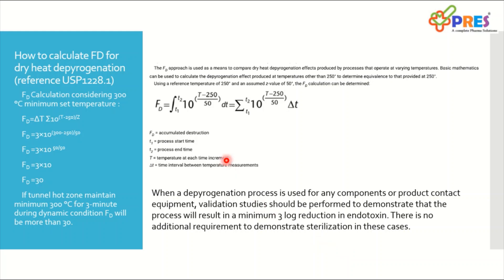Here is the formula for calculating the FD value: from time T1 (starting process time) to T2 (end process time), the integral of 10 to the power of (T minus 250) divided by 50, multiplied by delta-T (the time interval between temperature measurements). For example, if the set temperature is 300°C and exposure time is 3 minutes, the FD will be 30. This FD will vary based on changes in the 300°C and 3-minute set points. This calculation is shown to clarify how to calculate FD — not to specify that you must run your system at 300°C for 3 minutes. That is a myth; you need to validate with actual endotoxin recovery.